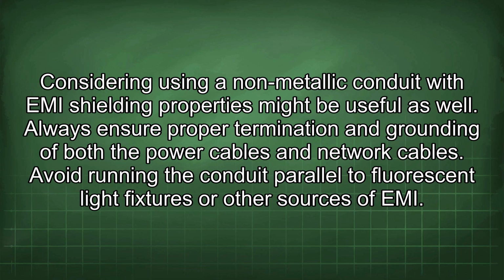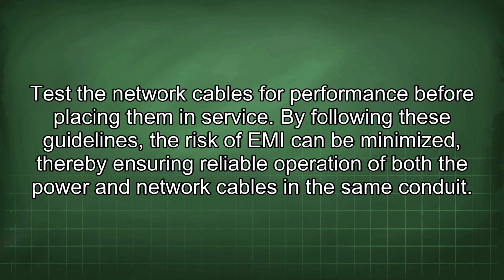Always ensure proper termination and grounding of both the power cables and network cables. Avoid running the conduit parallel to fluorescent light fixtures or other sources of EMI. Test the network cables for performance before placing them in service. By following these guidelines, the risk of EMI can be minimized, thereby ensuring reliable operation of both the power and network cables in the same conduit.